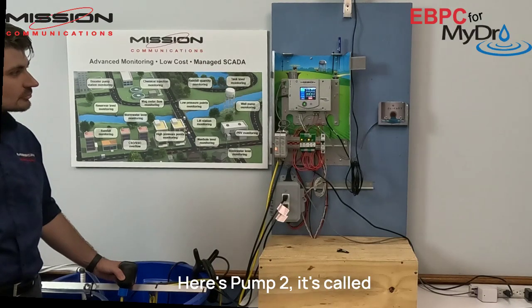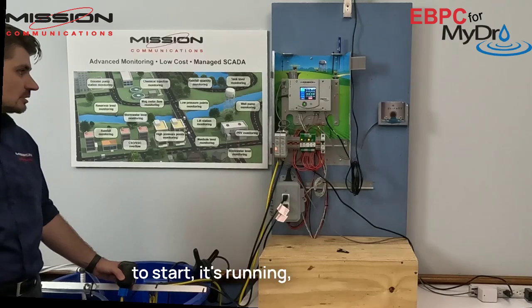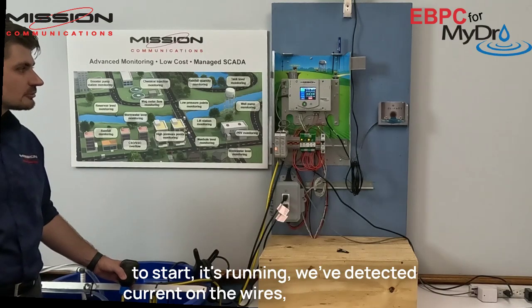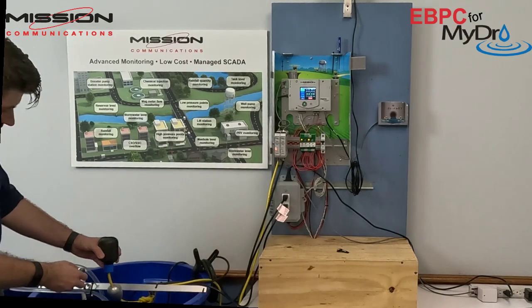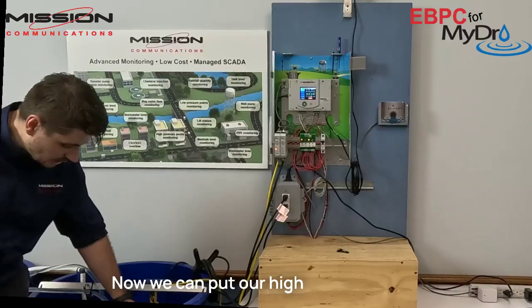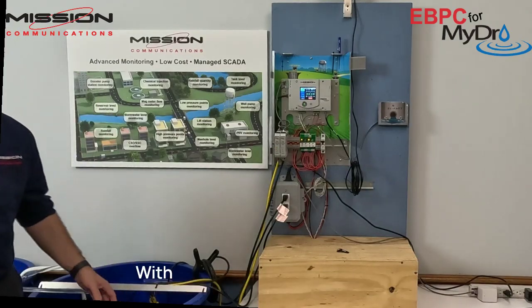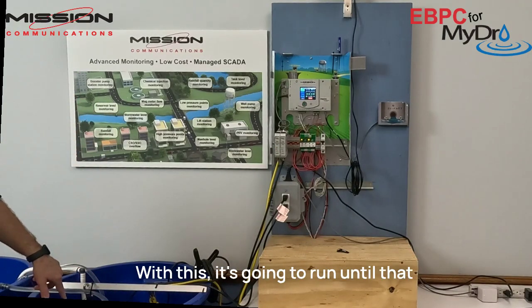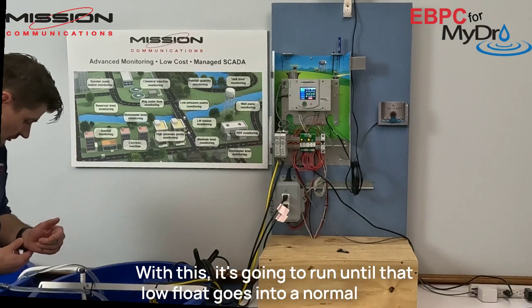Here's pump 2. It's called to start. It's running. We've detected current on the wires. We're good to go. And we can put our high float back down. With this, it's going to run until that low float goes into a normal state.